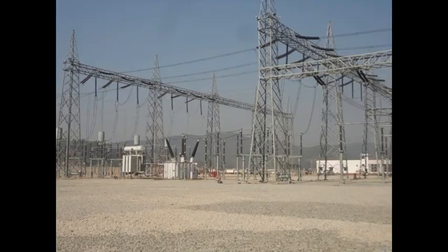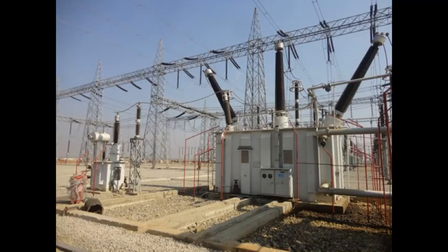The switchyard is part of the station level layout planning, and it requires a lot of space. Generally it is always preferred to have the switchyard in such a way that it is accessible to all the units for initial power supply as well as generated power evacuation.